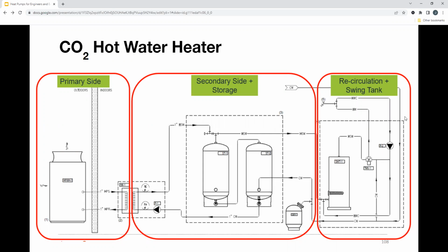And then the recirculation loop, typically you're going to have about 20 to 30% heat loss associated with that. So there's a swing tank included with electric resistance heat to make up those losses. So this is out here. This is an option if you are trying to completely electrify your building.